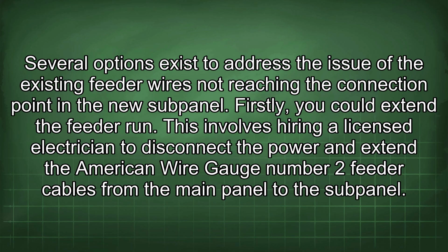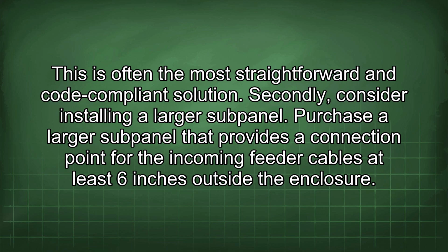Several options exist to address the issue of the existing feeder wires not reaching the connection point in the new subpanel. Firstly, you could extend the feeder run. This involves hiring a licensed electrician to disconnect the power and extend the American wire gauge number 2 feeder cables from the main panel to the subpanel. This is often the most straightforward and code-compliant solution.